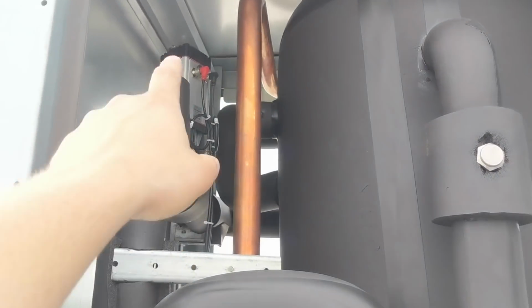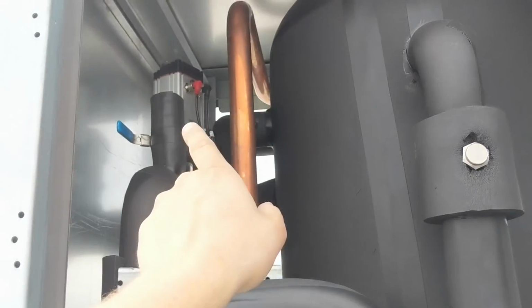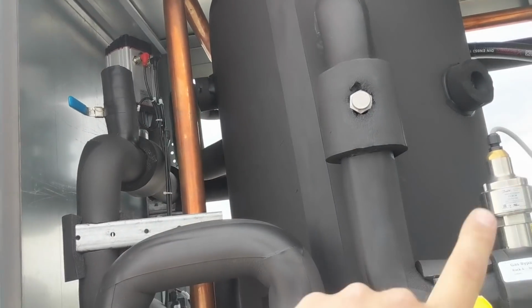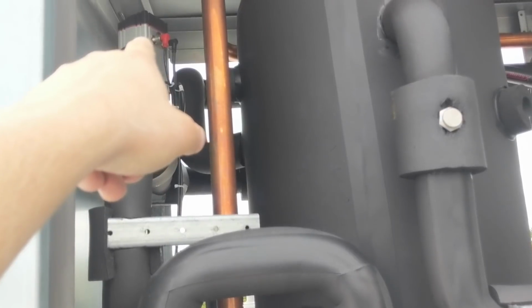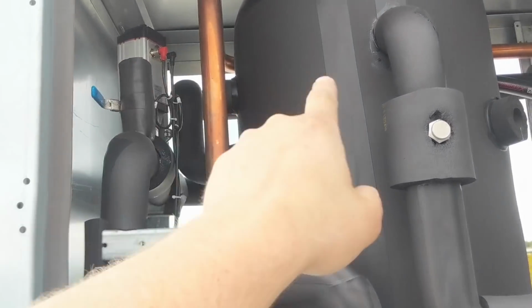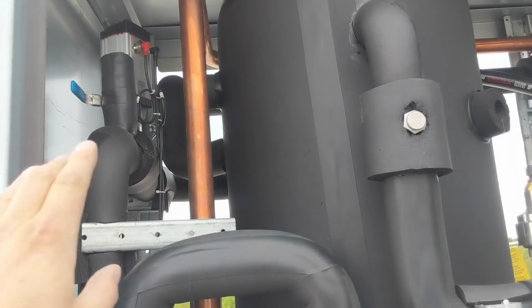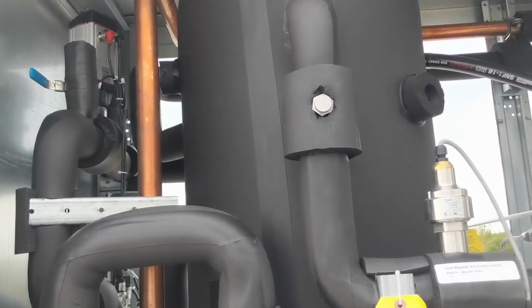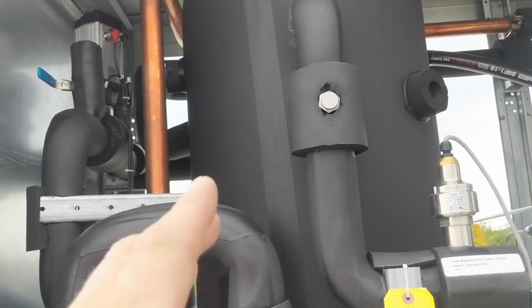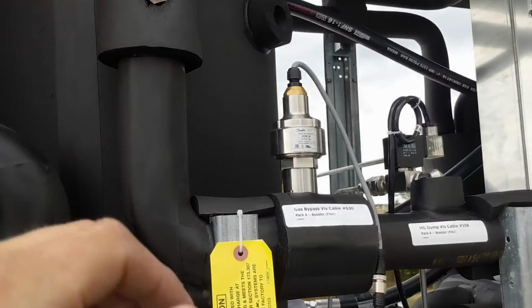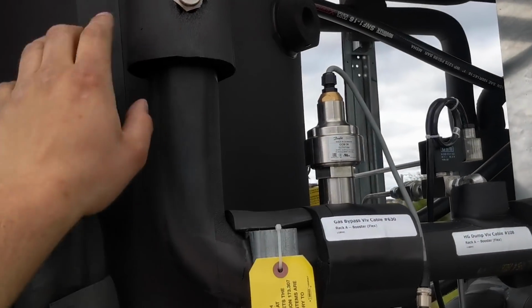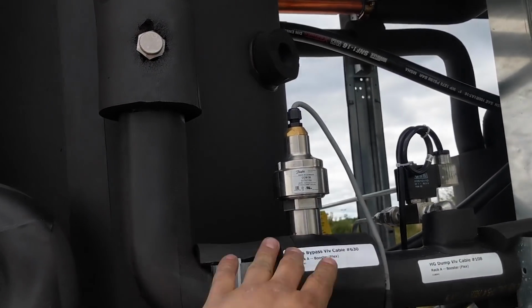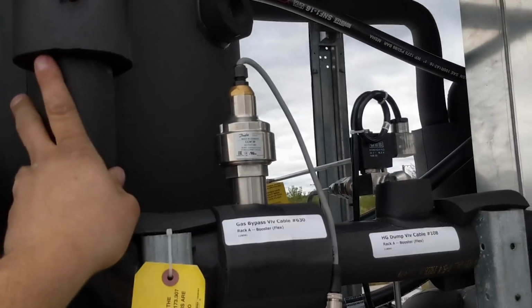So this valve is constantly shutting and opening. They're working in unison together to keep this tank at a certain pressure. This valve is constantly looking at the discharge pressure, drop leg pressure, and the tank pressure to make sure it doesn't high head the rack or starve a tank. And then this valve is constantly looking at the tank pressure to try to bleed out the tank and keep it at a certain pressure. That's how this is working.